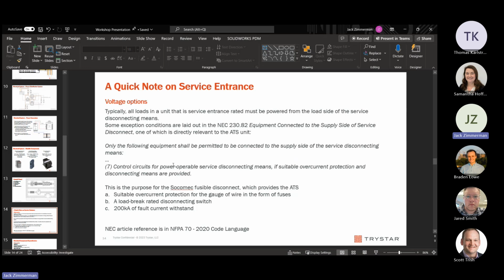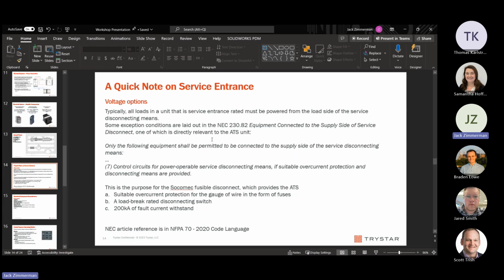Load break capable, and it can withstand, and this is the hardest one, 200,000 amps of fault current, because you need it to be rated up to what your enclosure is rated to, which in our case is 65 or 100. So we want it rated all the way up because we're pulling straight off the transformer. And this is a reference from the NFPA. This is 2020 code language. I checked 2023, it didn't change this section. So they added a couple to this article, but yeah. So we have to know that we are doing something that's typically against National Electric Code, so we have to be very strict in how we are handling it within the exception that's laid out within the code.